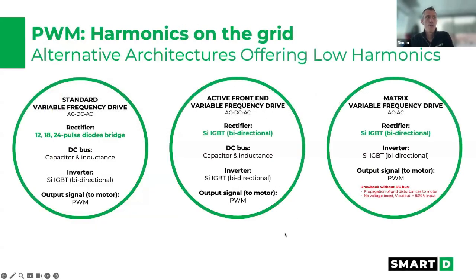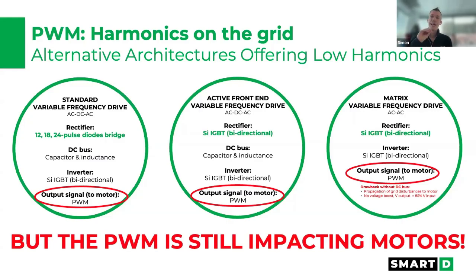Now, the matrix architecture does not have a DC bus, so that exposes potential issues. If you have a disturbance on the grid, that will go directly to the motor on one side. And on the other side, because you don't have that DC bus, you don't have that potential boost. So you're limited to an 80% voltage output, which can be problematic in some cases, and certainly in long cable applications, which are of interest to us today. But in all of these cases, they are still PWM-based solutions. So on the motor side, you will have pulse width modulation impacting the motor.